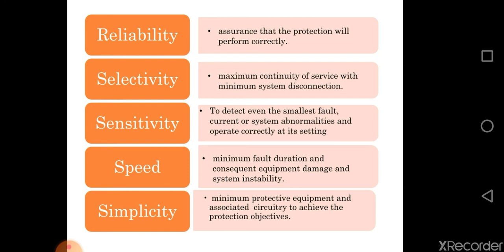First, reliability. Assurance that the protection will perform correctly. Selectivity. Maximum continuity of service with minimum system disconnection. Sensitivity. To detect even the smallest fault, current or system abnormalities and operate correctly at its setting. Speed. Minimum fault duration and consequent equipment damage and system instability. Simplicity. Minimum protective equipment and associated circuitry to achieve the protection objectives.